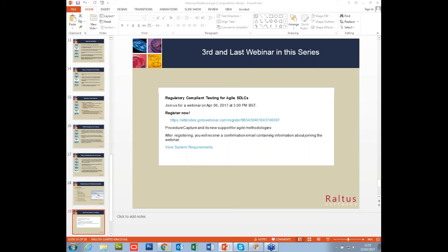And although this doesn't come out of FDA guides, I think the other big advantage of requirements traceability is actually during a regression analysis. If you're doing a regression analysis, which is something the regulators are hot on, the ability to quickly trace backwards and forwards matters: we've got a change in requirements here, that's implemented in this configuration or that code. If I change that, what other requirements are linked to that configuration or code, and should I retest those as part of my regression testing? Having good requirements traceability enables you to ask those questions and answer them relatively quickly.